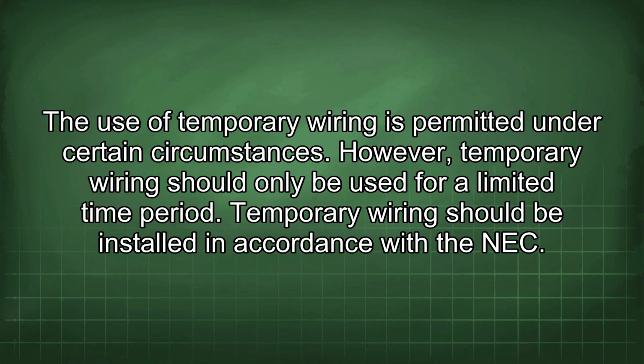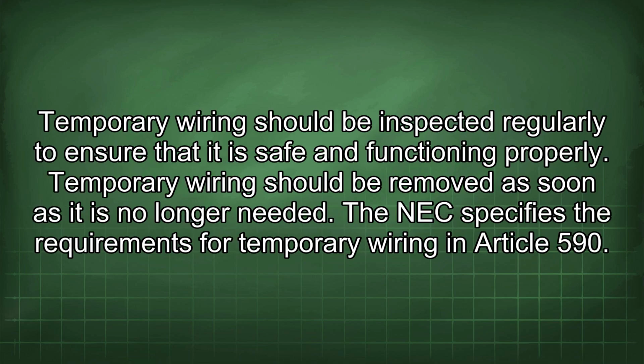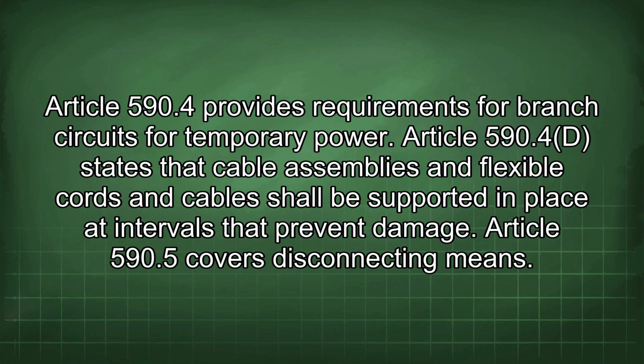The use of temporary wiring is permitted under certain circumstances. However, temporary wiring should only be used for a limited time period. Temporary wiring should be installed in accordance with the NEC. Temporary wiring should be inspected regularly to ensure that it is safe and functioning properly. Temporary wiring should be removed as soon as it is no longer needed. The NEC specifies the requirements for temporary wiring in Article 590. Article 590.4 provides requirements for branch circuits for temporary power. Article 590.4(D) states that cable assemblies and flexible cords and cables shall be supported in place at intervals that prevent damage.